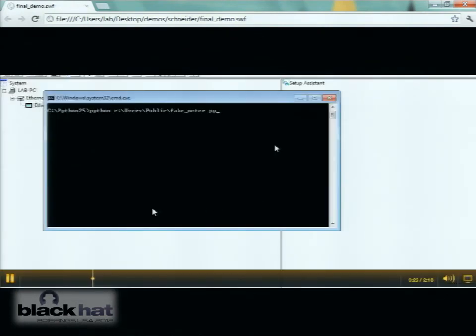So we are going to pose as a fake meter in order to receive the backdoor password from the software, because my point is that software has been used by the Schneider support staff to troubleshoot customers, and the same version with some capabilities disabled was deployed to the public.